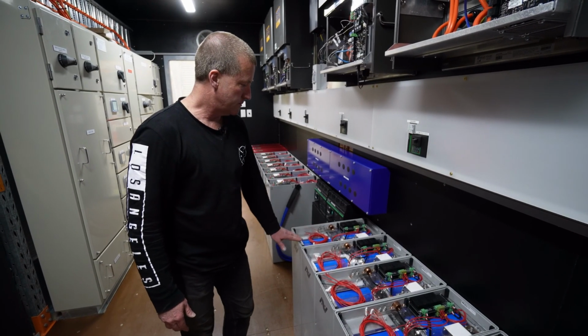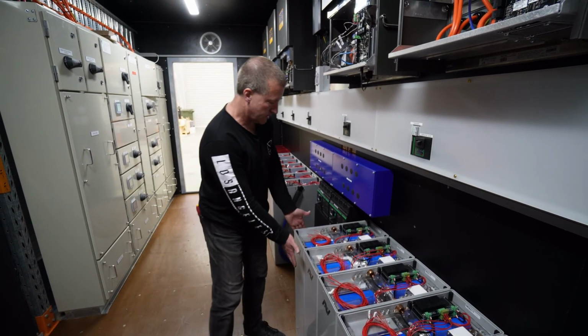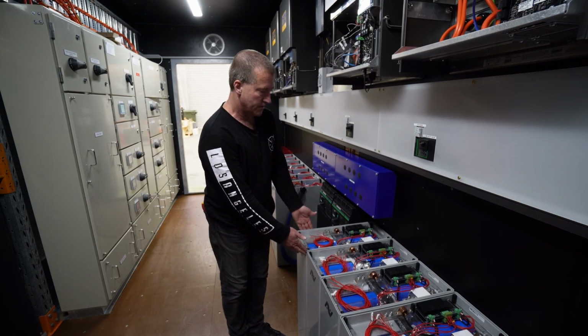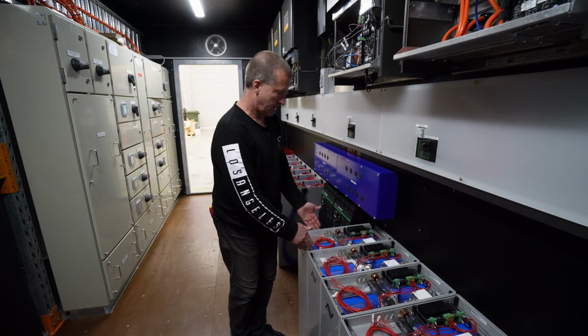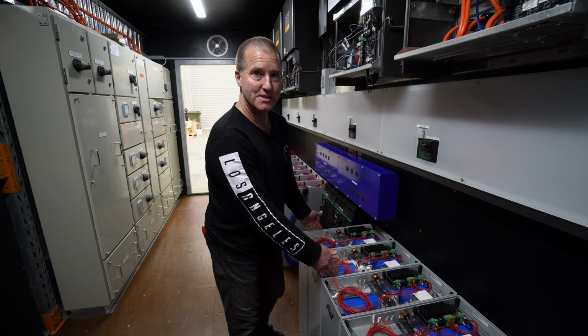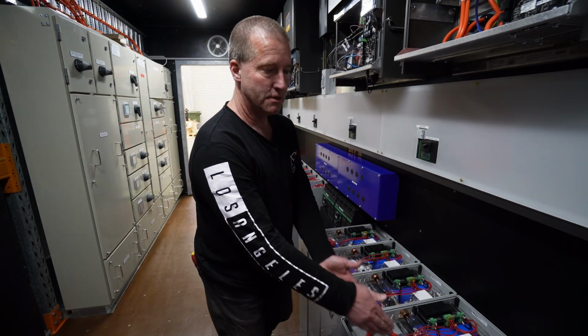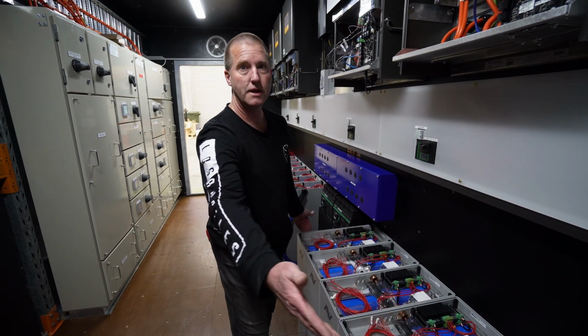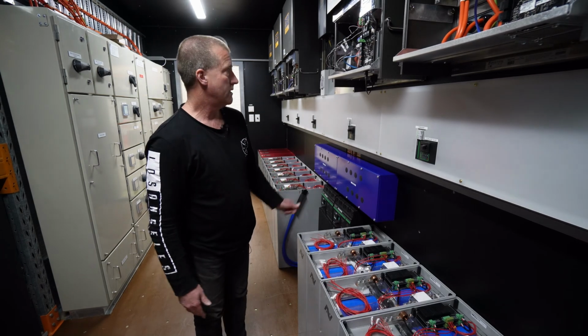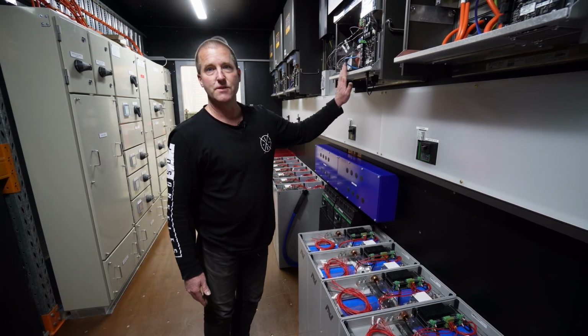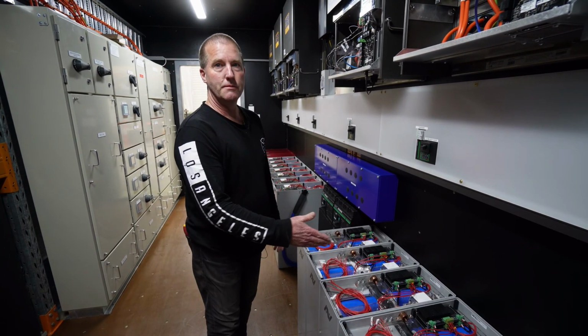So each one of these modules is series connected. If you look closely, this one's 13.8 volts, 6.2 kilowatt hours, and it's series connected to another one which is 27 volts, 40 volts and so on, until you get to the end at 138 volts across the bus. These inverters here work from 100 to 170 volts, so it's a good sweet spot in the middle.